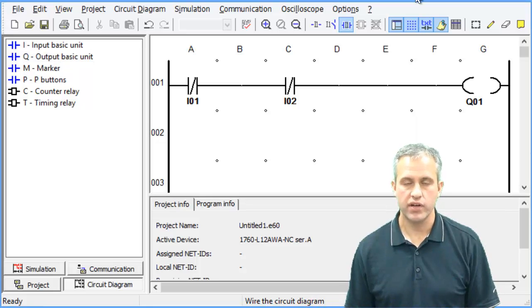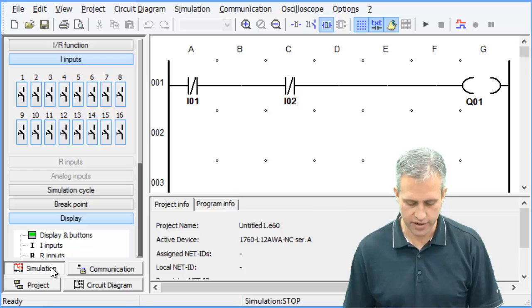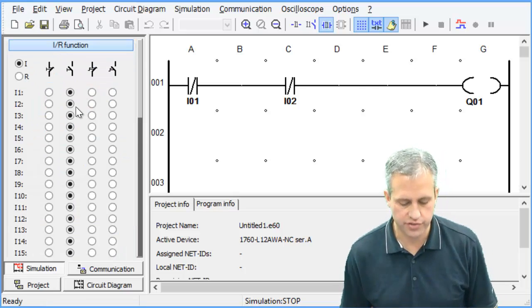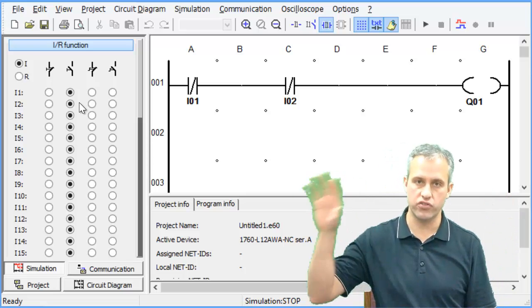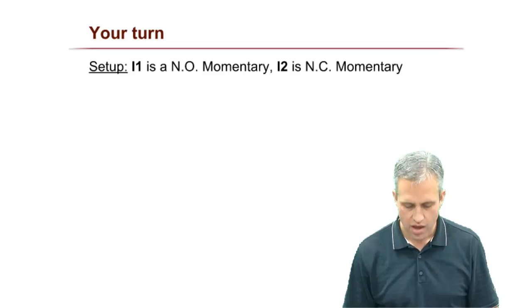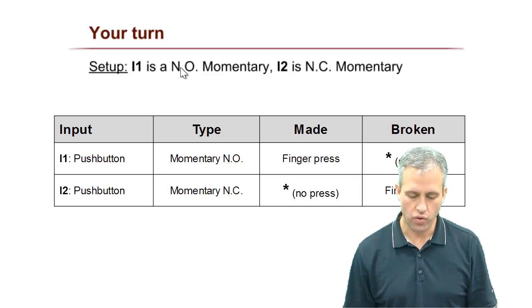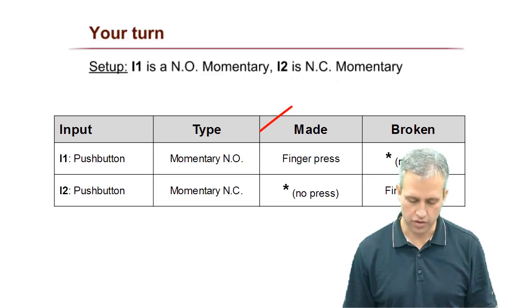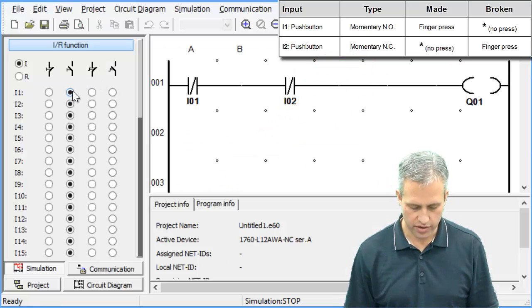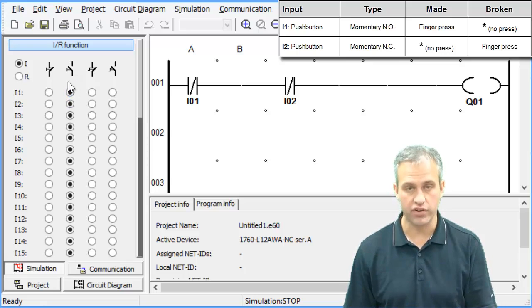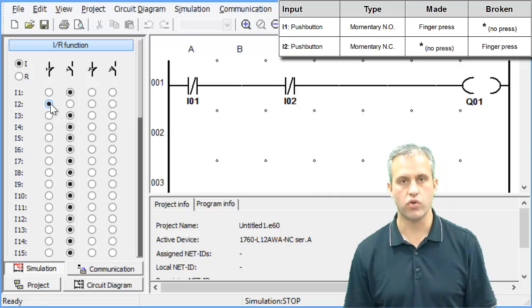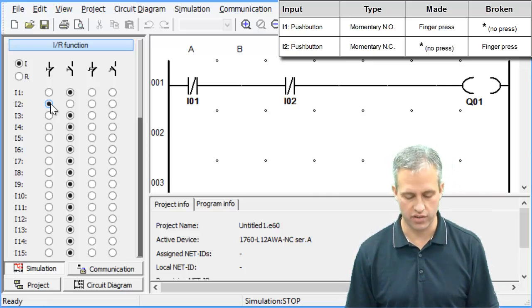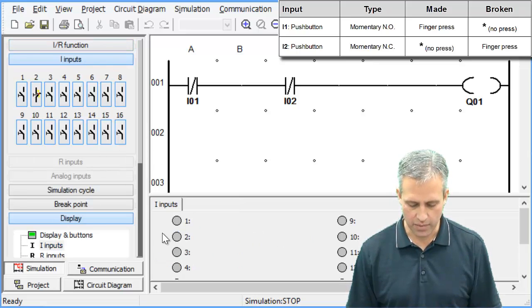This should be the circuit that will make this work for question number one. Now we need to check to see if this thing actually works. We'll head over to the simulation area. The first thing you need to do in a simulation is make sure that your input types actually match the real world. If you remember from the problem statement, it said I1 is normally open momentary, I2 is normally closed momentary. So I1 was normally open momentary, that's the default. Then I2 was normally closed momentary. Make sure you set those things as appropriate.